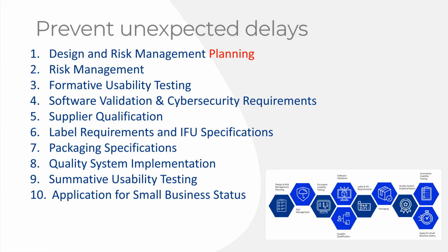So what do you need to do? You need to first identify what your user interface is. Identify what your user groups are, your patient population, your use environment. That's just definitions, and that's going to take you a few pages. Then you're going to have to do brainstorming to identify tasks. So what are your use-related tasks? Then you do a task analysis and then identify use errors. You would look at complaints. You could look at adverse events. You could look at competitor products. You could do formative testing.